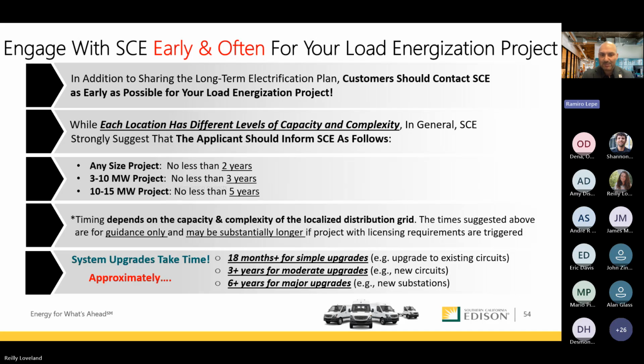Now let me put this in perspective — site upgrades do take time. If we're upgrading existing circuits, meaning circuitry already going to your facility because there's not enough power available, that's 18 months plus. If we need to run a brand new line from the substation out to your project, that's approximately 3 years plus.